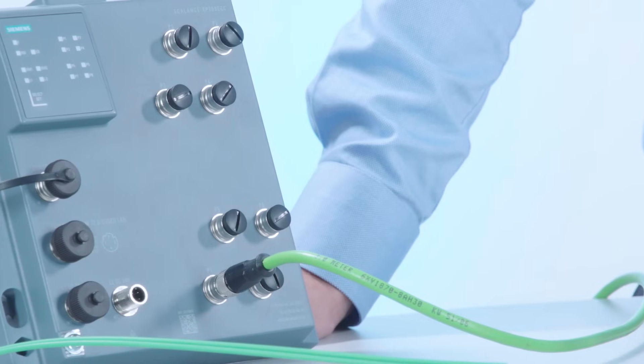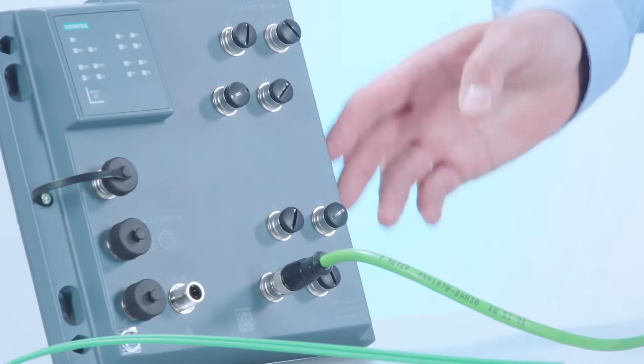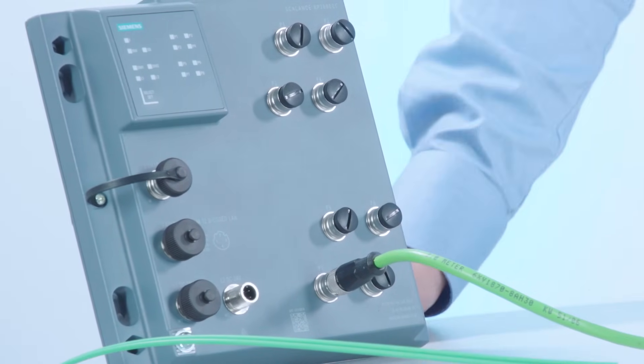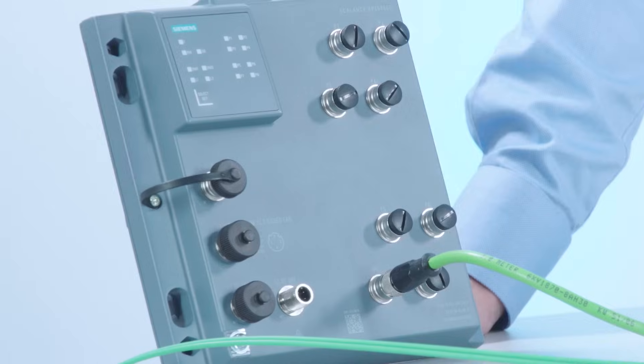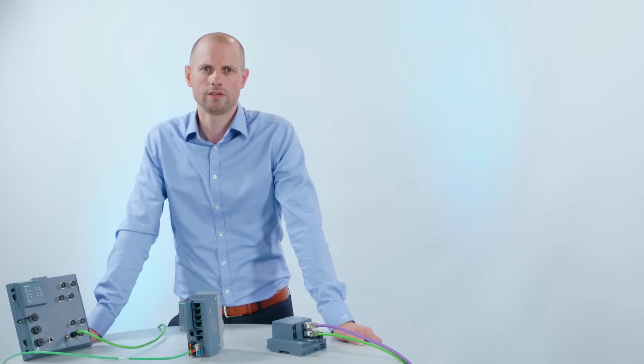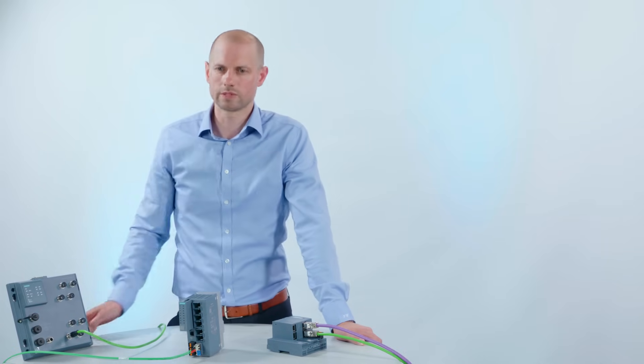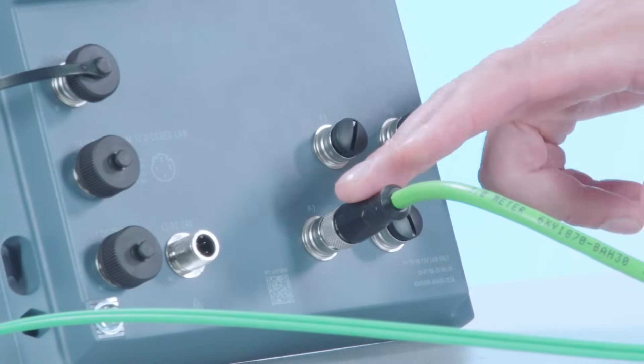Scalance XP200 switches cover another important field of application. They provide a metal enclosure and a flat design and are equipped for use outside the control cabinet. In real terms, this means that the devices are connected by robust M12 plugs, which fulfill an IP65 degree of protection.